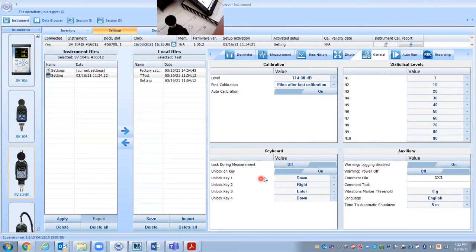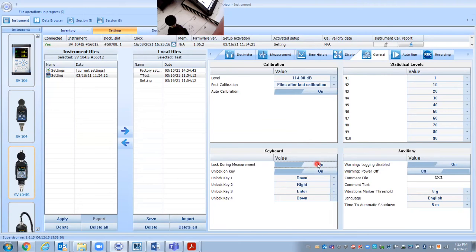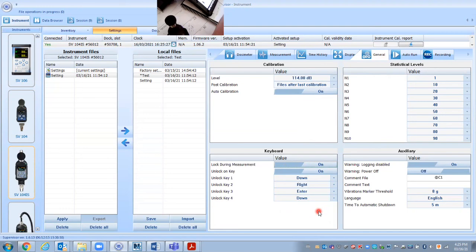This is actually maybe this one here. This would be if you want to have the unit when you start to, when the dosimeter is turned on to measure, if this is turned on, it will automatically lock. And there's another video that shows, but basically to unlock it, this is the sequence here. So the down, right, enter, down key will unlock it. So you can start and stop it.